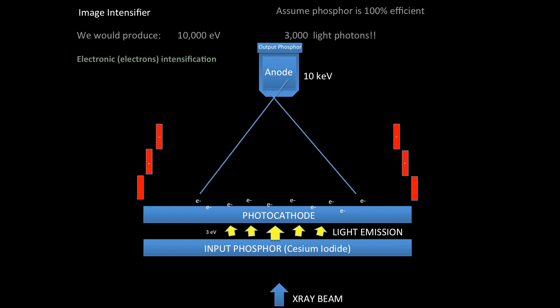Therefore, by this potential, assuming we have a phosphor that's 100% efficient, which is really not the case in reality but approximately, you would be producing 10,000 electron volts and yielding 3,000 light photons. So there's significant magnification going on here as a result of the potential that we generate through the acceleration of electrons towards the anode.